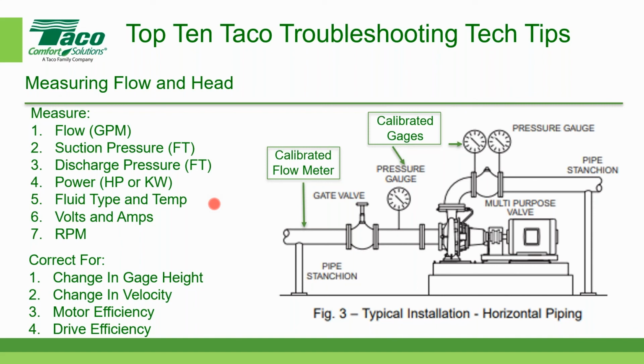especially if you have glycol. If you have a chilled water system that's pumping a water glycol solution, the temperature will have a fairly significant impact on the amount of power that it needs to move that solution. If the temperature is low in a chilled water system, it will have a significant impact. Turns out if the fluid temperature is relatively high, let's say it's 190 degrees, and it's a water glycol solution, it has very little effect on the power. So that's a piece of data. And like I said before, we want to know the volts and the amps and the RPM. And what do we need to correct for when we get this field data? Well, one of the things we need to make sure of is that we make the correction in gauge height.